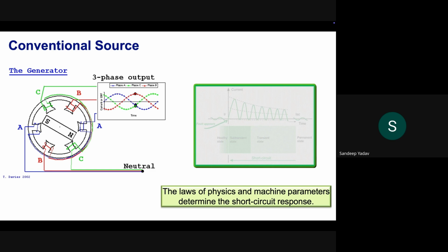It can supply a large amount of reactive power and a good amount of short circuit power whenever it meets any contingency. Whenever there is a terminal fault, or any fault at the electrical terminals of the machine, because of the changes in the inductances we see varying levels of impedance. For the initial 1 or 2 cycles, the impedance is known as the subtransient impedance or subtransient reactance. It is usually very small, and that is why the fault current this generator feeds in the initial few cycles is much higher. Depending upon at what point on the wave the fault happens, the DC component will vary. So in the subtransient state the fault current is very high.